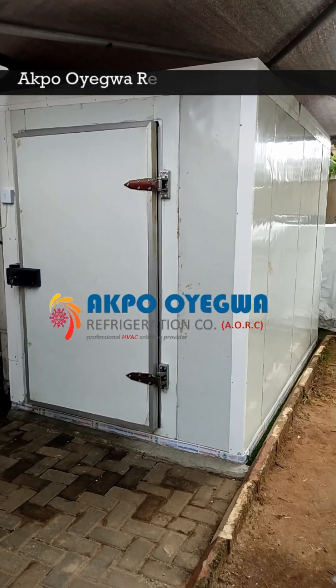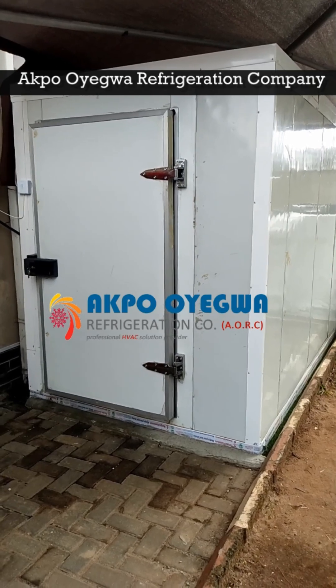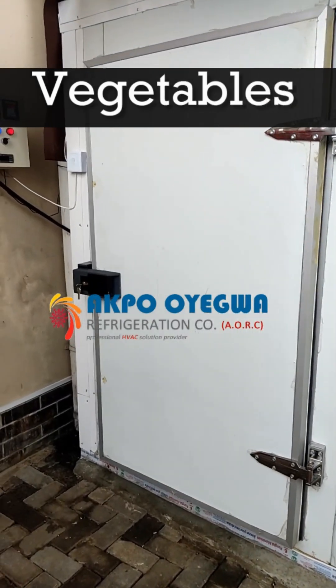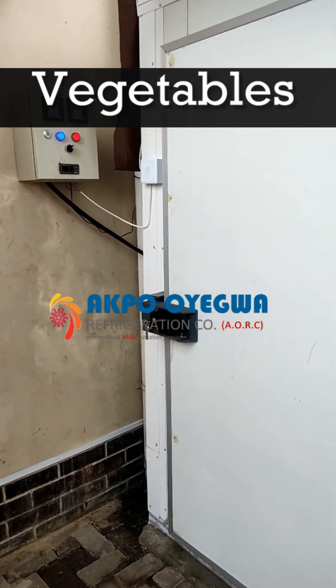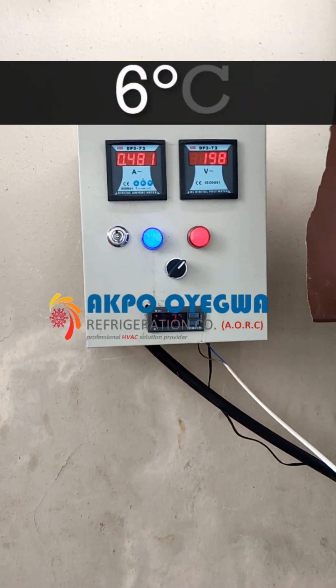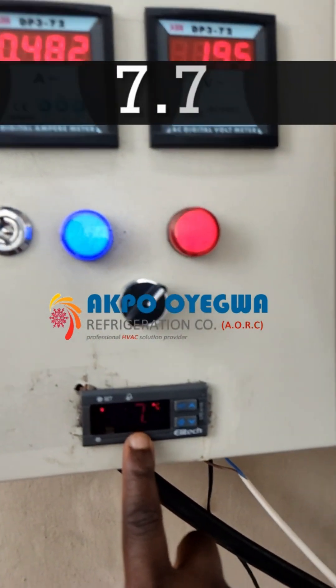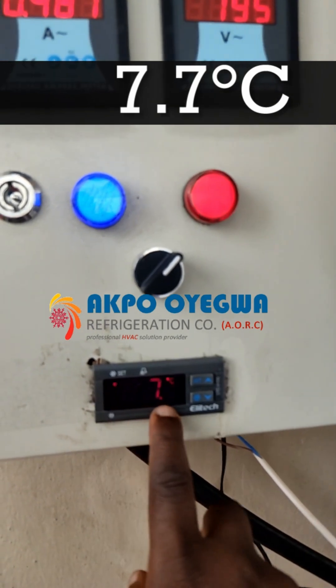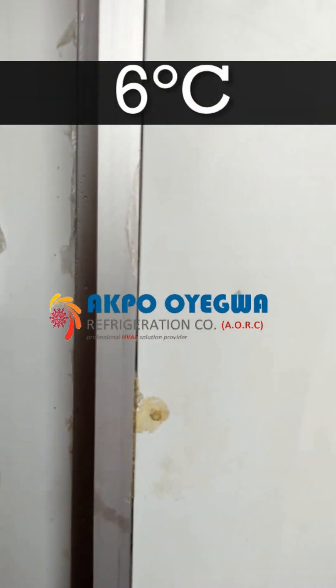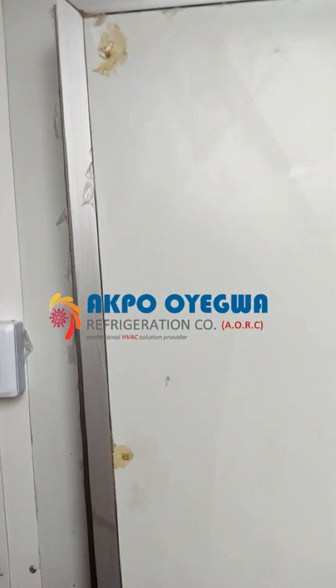Hi once again. This is a cold room built by Akpo Oyegwa Refrigeration Company. You can see this is a high quality cold room. The customer intends to store vegetables. The temperature the client has requested is 6.6 degrees Celsius, and right here on the screen we have 7.7 degrees Celsius — so we are approaching 6 degrees Celsius at the moment.